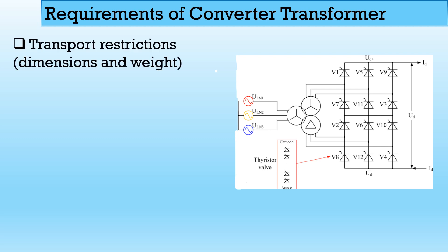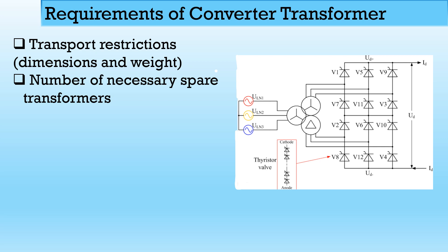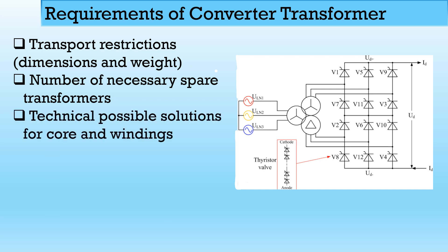If you design a single unit three-phase transformer, its dimension and weight will put restrictions on transportation. The number of necessary spare transformers is also a concern: if you use a single three-phase transformer, you need one spare of that large size. But if you use three single-phase two-winding transformers, then one single unit is sufficient as a spare. Technical possible solutions for the core and winding are required because the rating of the converter transformer is high.